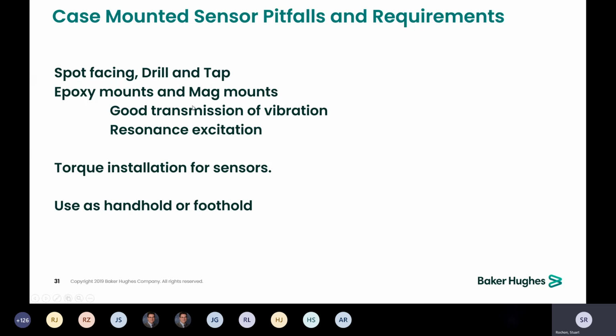Mag mounts, I've seen some setups where it's quite a stack of components between the magnet and the adapter plate to adapt the magnet to the sensor, and then the extension cable and everything, and it can get 6-7 inches. You just have to be careful and make sure that you're not getting motion of the sensor that is not related to the actual motion of the machine. Nothing's dragging it down.